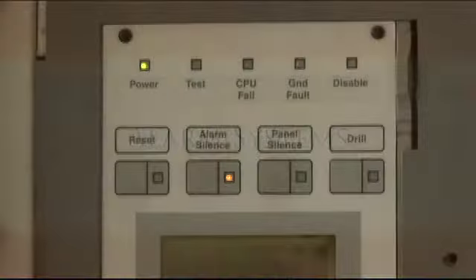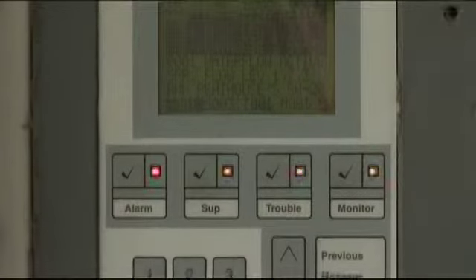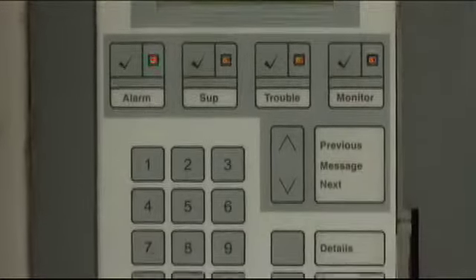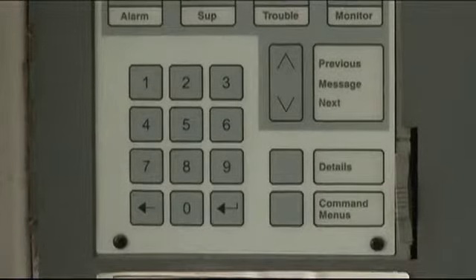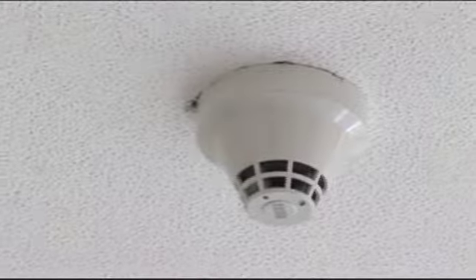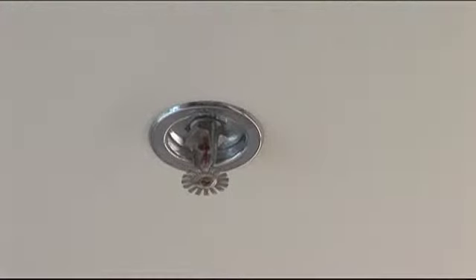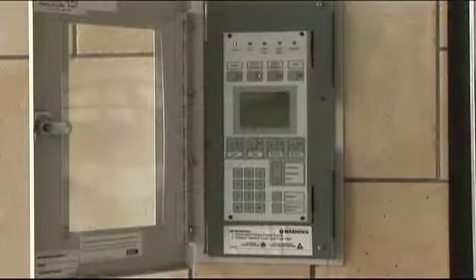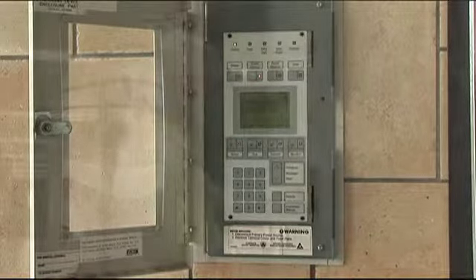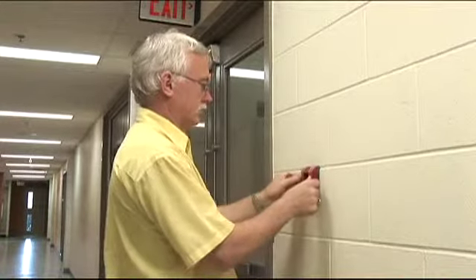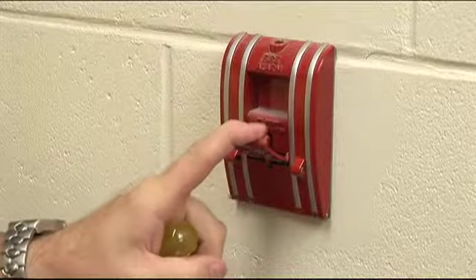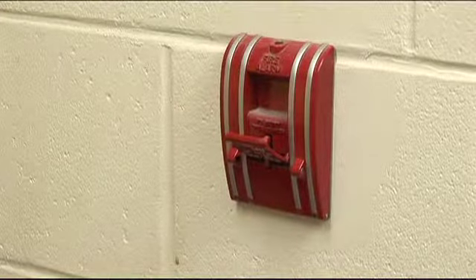Schools with more than 40 occupants are required to have a single-stage fire detection and alarm system. A single-stage system is one that activates an alarm signal, alerts occupants of a potential fire emergency, and indicates evacuation. Smoke detectors and sprinkler heads located throughout the school provide automatic fire detection. The fire alarm system may also monitor the sprinkler. Using one of the pull stations located at exits throughout the building can also manually activate the alarm system.